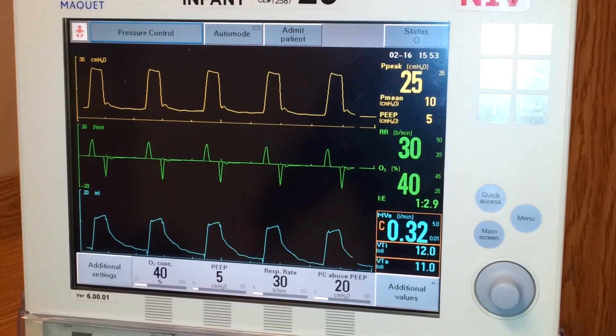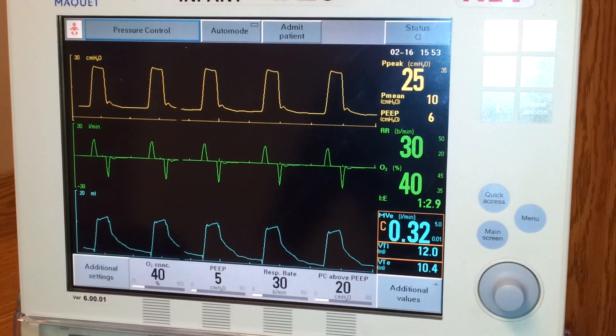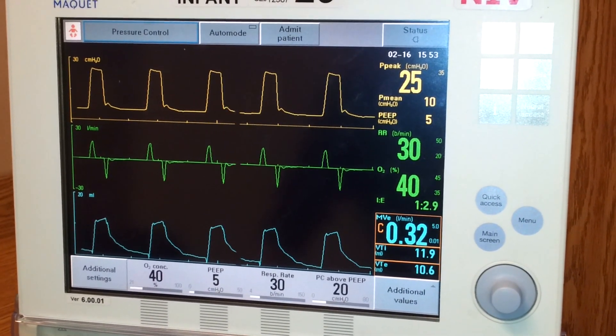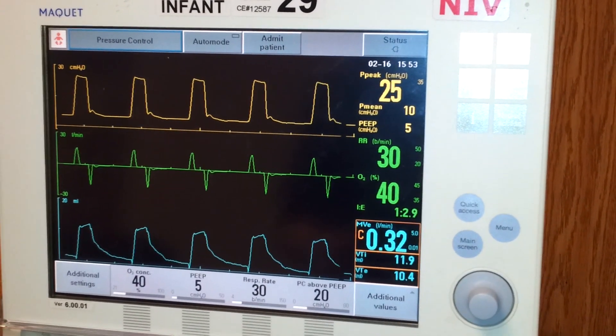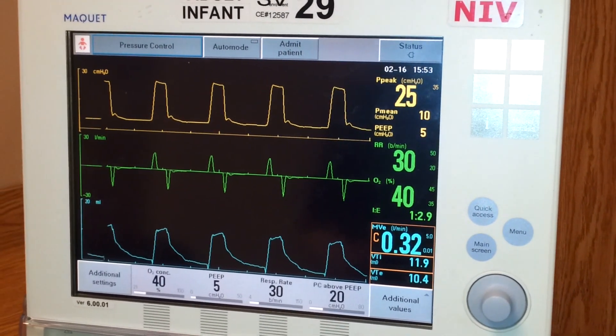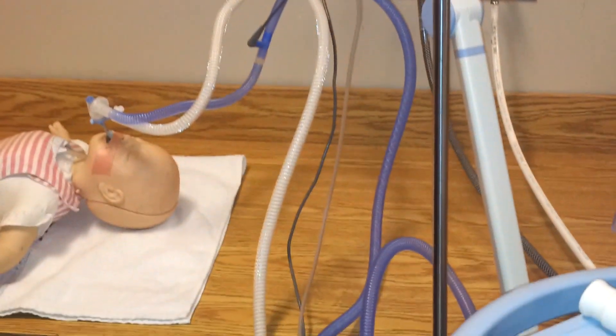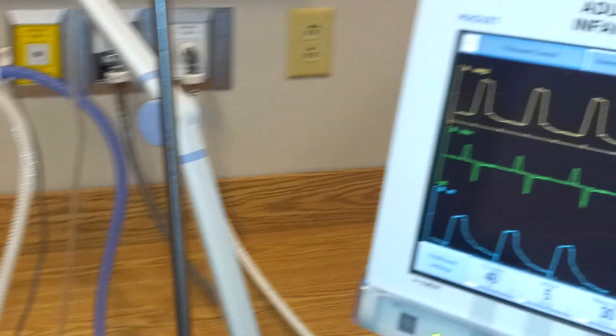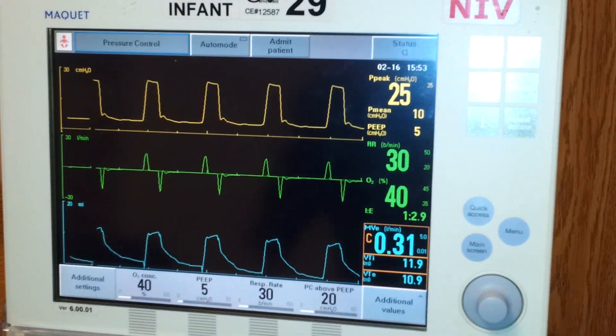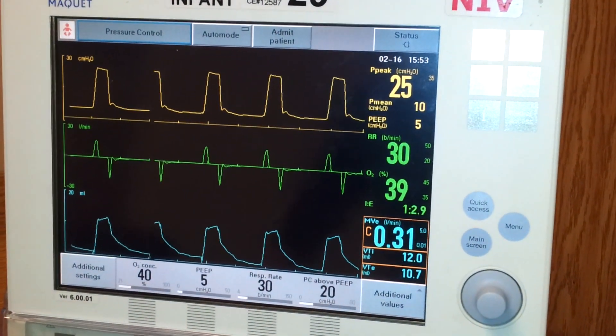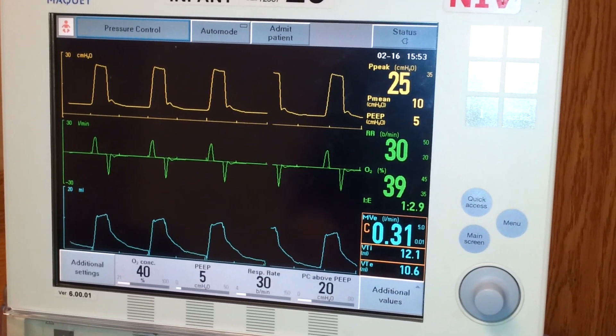So back to how tubing compensation works. If a ventilator is not tubing compensated, the amount of volume that the ventilator sends is not actually what the patient will receive — some of that volume will be lost to the tubing. A lot of new ventilators, like the Servo-I, will calculate the tubing compliance for you in its pre-use check and send extra volume to compensate for what's lost in the tubing. The volume that actually makes it to the patient is known as effective tidal volume.